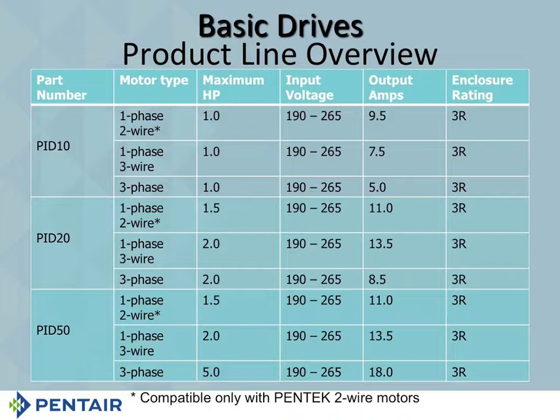But you can get a PID 10. Now, notice it says maximum horsepower is 1. And then it goes over on the other side there, and you see where it says output amps. I've always tried to train everybody when I talk to people: you always size a drive based on amps. You do not size a drive based on horsepower. Now, that being said, you'll notice the PID 20 is designed around a 2 horsepower, both single and 3-phase. And you'll notice also that it is designed around 8.5 if it's 3-phase. It's designed around 8.5 max load amps output.